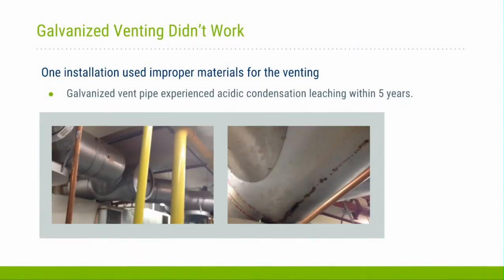The contractor, it was one of those things at the end of the contract where you don't have a bunch of money left, and this building suffered from that. It was kind of said, oh, you'll be fine with the galvanized stack that you've got going. Once again, you can see where it's all breached together on that one slide. Well, you'll see on the other picture that's how acidic the condensing water is that it's being put up the vent.